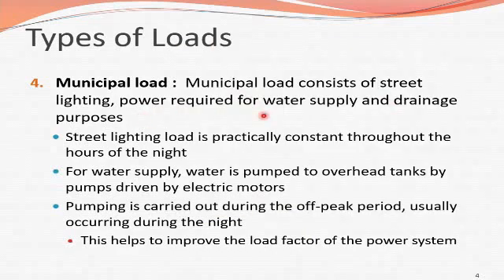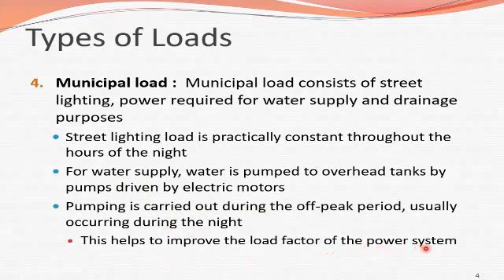The municipal load consists of street lighting and power requirements for water supply and drainage purposes. Street lighting load is practically constant throughout the hours of the night. For water supply, water is pumped to overhead tanks by pumps driven by electric motors. Pumping is carried out during the off-peak period, usually occurring during the night, which helps to improve the load factor of the power system.